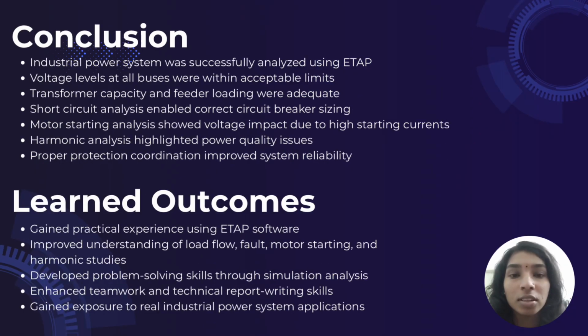For this project, an industrial power distribution system was successfully analyzed using ETAP software. The load flow analysis showed that all bus voltage levels were within acceptable limits, indicating that the system was properly designed. Transformer capacity and feeder loading were also found to be adequate for the connected loads. Short circuit analysis was carried out to determine fault current levels, which helped in selecting suitable circuit breakers.